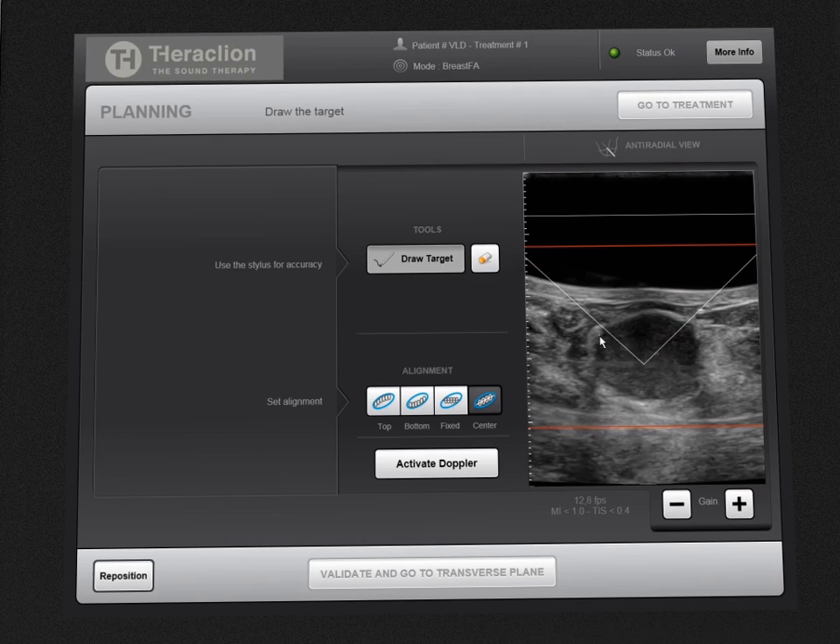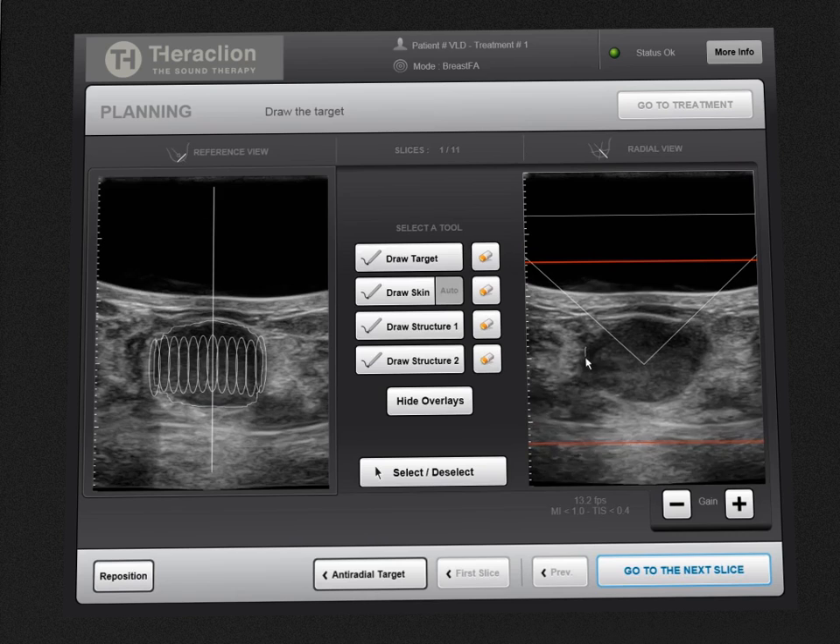At this point, the treatment itself can be planned. To start, the operator outlines the breast fibroadenoma over the real-time ultrasound image in two different planes. Theraclion's smart software automatically suggests a set of adjacent slices within the target by reconstructing the fibroadenoma volume and determines precise treatment sites. Skin limits are also outlined.